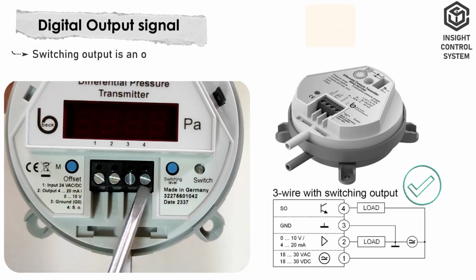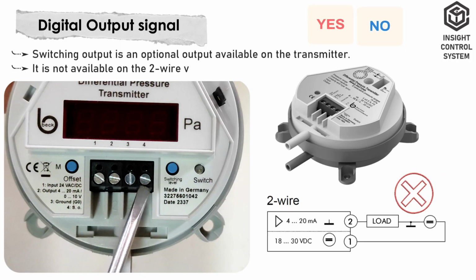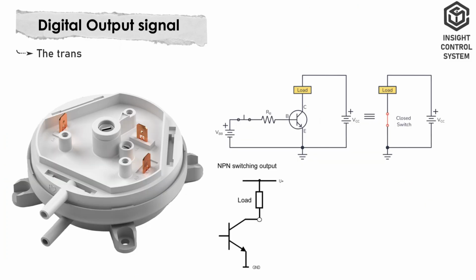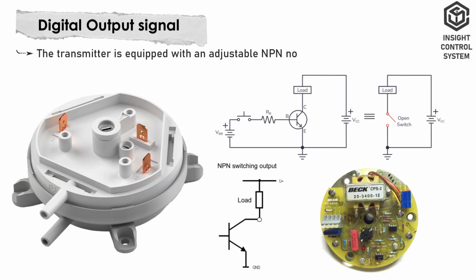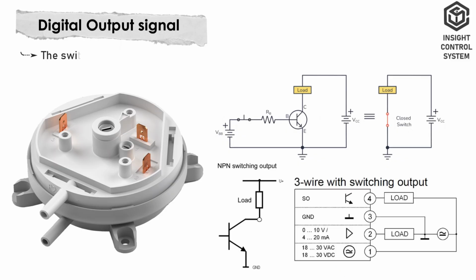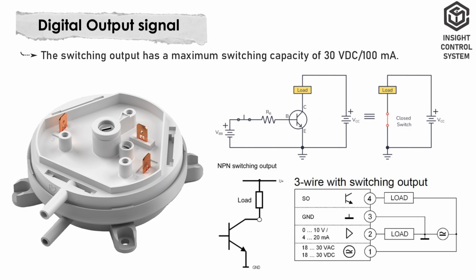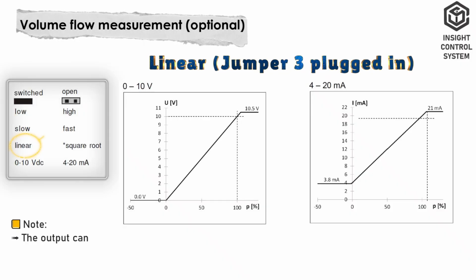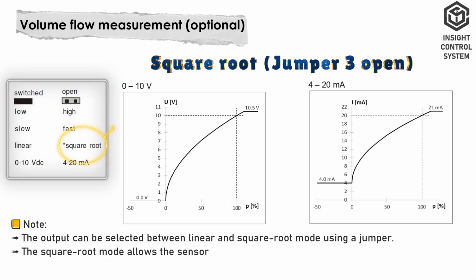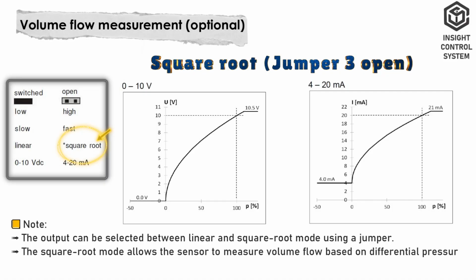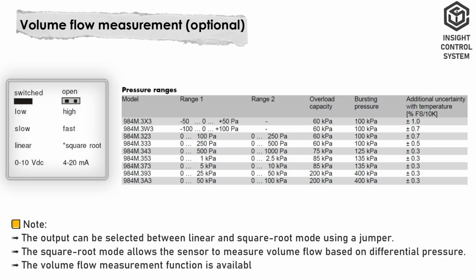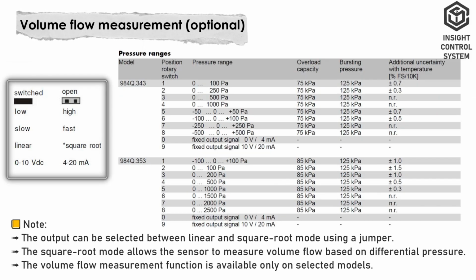Digital output signal. Switching output is an optional output available on the transmitter. It is not available on the 2-wire version. The transmitter is equipped with an adjustable NPN normally open (NO) transistor switching output. The switching output has a maximum switching capacity of 30 volts DC and 100 milliamperes. Note: the output can be selected between linear and square root mode using a jumper. The square root mode allows the sensor to measure volume flow based on differential pressure. The volume flow measurement function is available only on selected models.